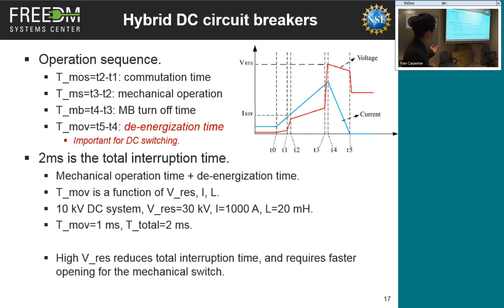Okay, let's look at the total time for this DC interruption. We have observed that the commutation time and the main breaker turn-off time are very small compared to the other two components. So we say the total time is approximately the mechanical operation time plus the de-energization time. And the de-energization time, which I denote as TMOV, is a function of the residual voltage, the inductance of the system, and the current level.